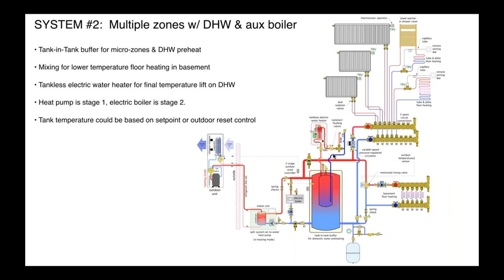Here's one, a little more elaborate. Again, these are pulled right out of Hydronics 27. We've got an electric boiler supplementing a split system air-to-water heat pump. We've got the tank-in-tank here. So we're getting domestic water preheat in the inner tank, topping it off with the electric water heater. And then we're going out here. We've got one manifold station doing home run circuits off to a variety of low temperature heat emitters.